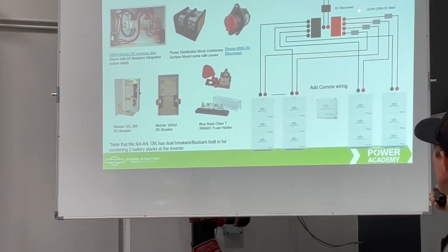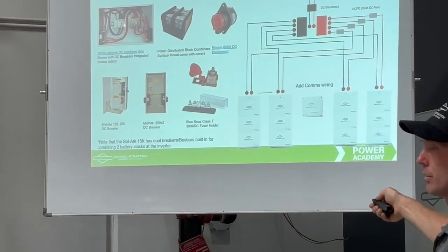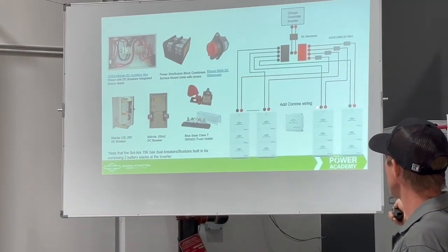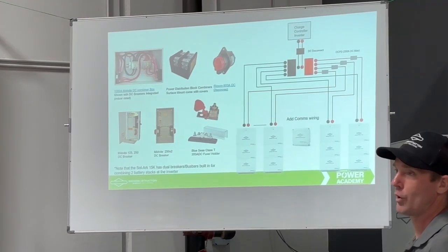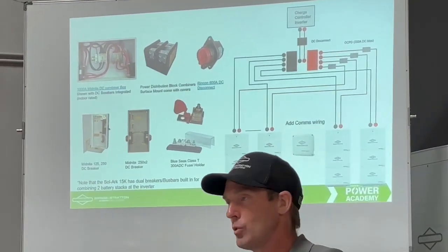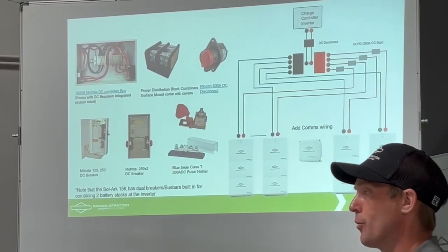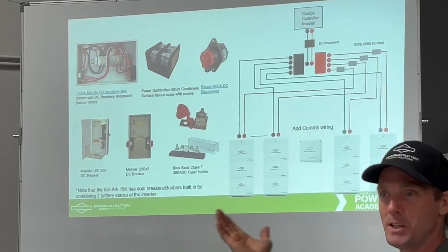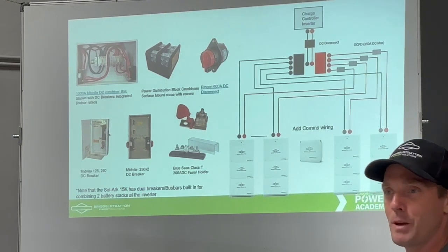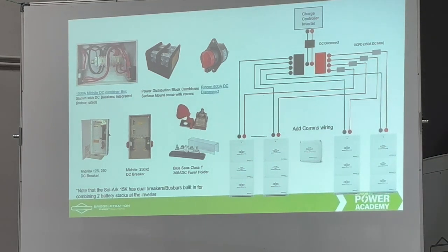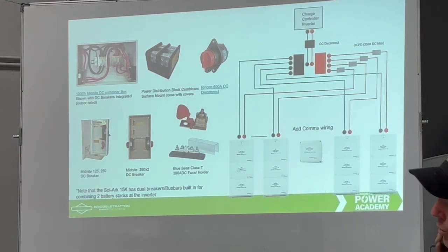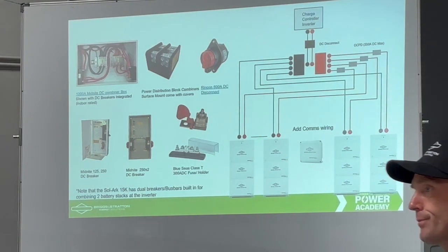This diagram represents the Midnite combiner here. If you have 4 stacks, on a DC device you only need single pole overcurrent protection—you only have to interrupt one side of the circuit. Some people do breakers on both sides, costing themselves extra by doing the negative side too, but you only need it on one pole, positive or negative, doesn't matter which. Those blocks represent the overcurrent protection.